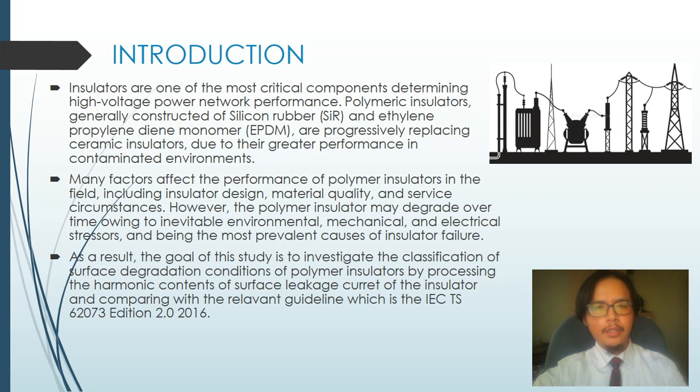As a result, the goal of this study is to investigate the classification of surface degradation condition of polymer insulator by processing the harmonic contents of surface leakage current of the insulator, and then comparing with the relevant guideline, which is the IEC-TS 62073 edition 2016.